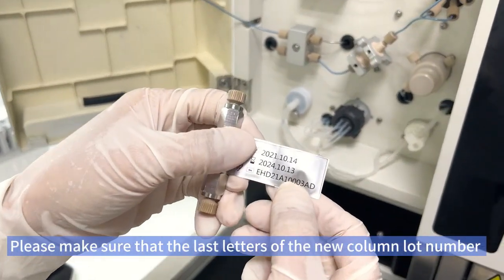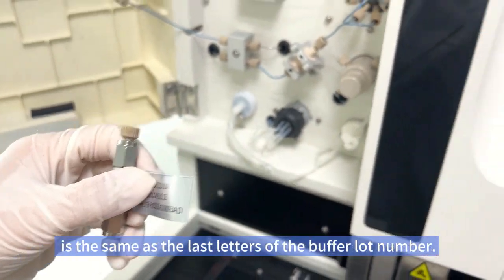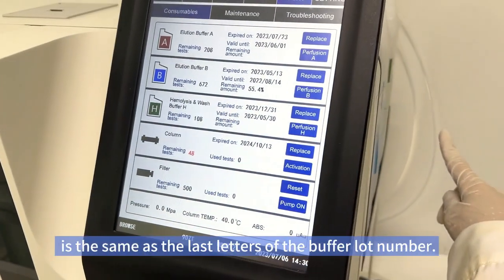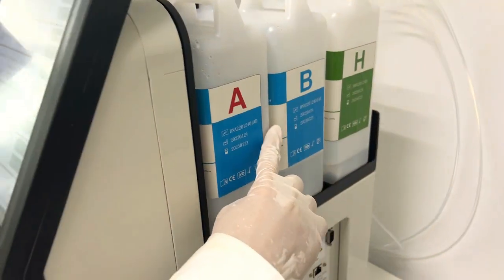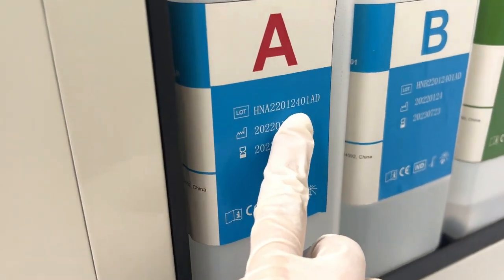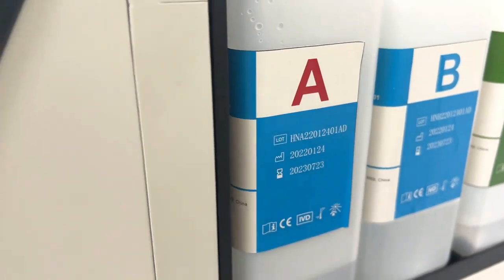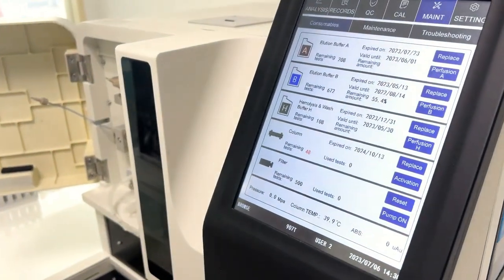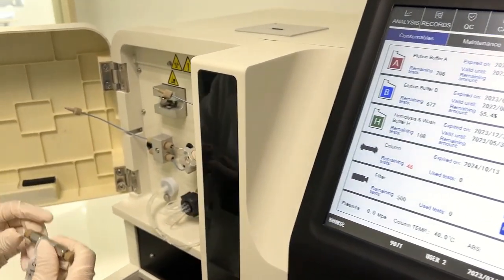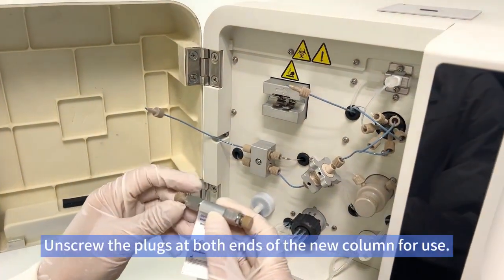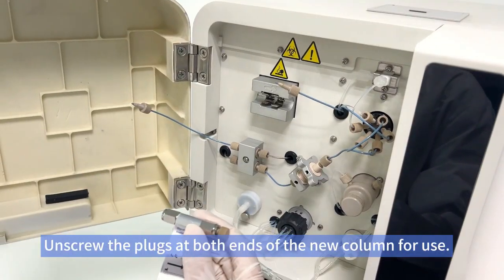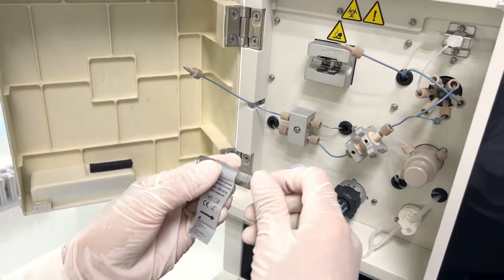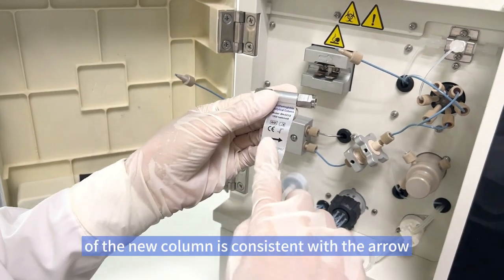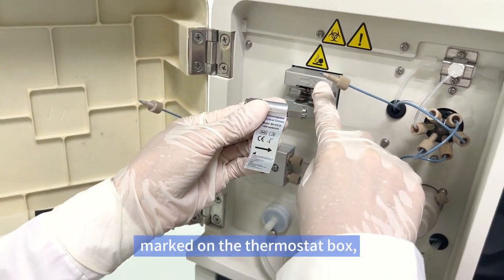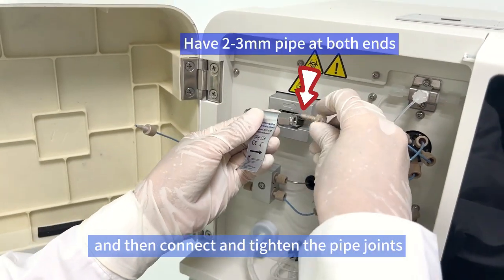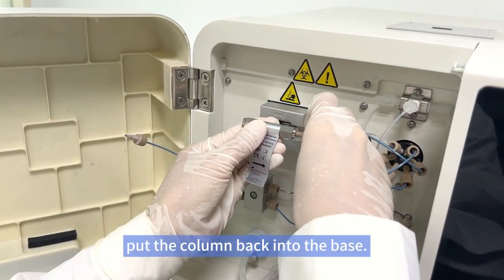Please make sure that the last letters of the new column lot number are the same as the last letters of the buffer lot number. Unscrew the plugs at both ends of the new column for use. Make sure that the flow direction arrow of the new column is consistent with the arrow marked on the thermostat box, and then connect and tighten the pipe joints. Put the column back into the base.